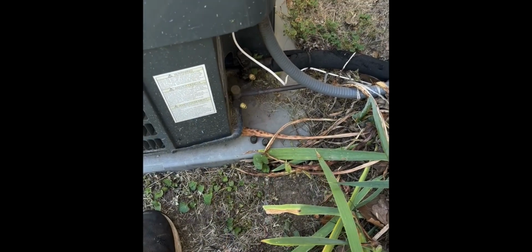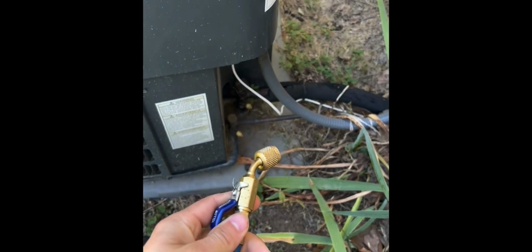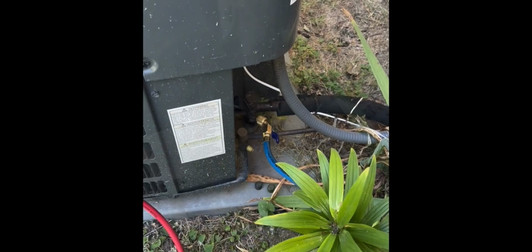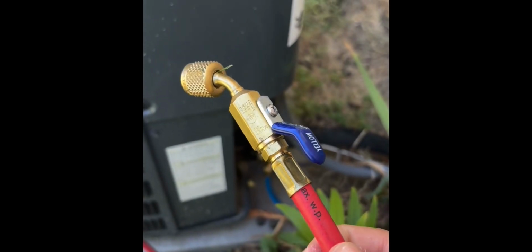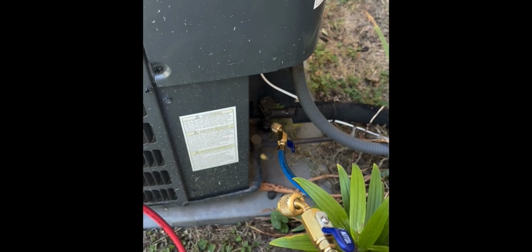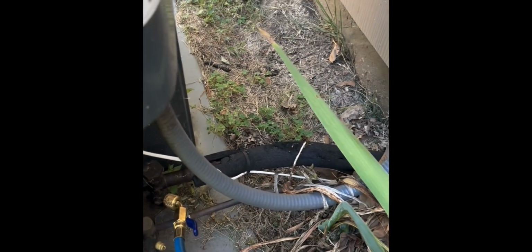The first thing you are going to want to do is hook the blue low pressure side hose to this thicker copper tube down here to get your low pressure readings. And I'll show you how to do that quick. You want to make sure you got it on there straight so you get a nice seal and you don't cross thread any of the threads or anything like that. Then you are going to want to hook up this red hose to the thinner copper line down there, known as the liquid line. The thicker copper line is known as the suction line.